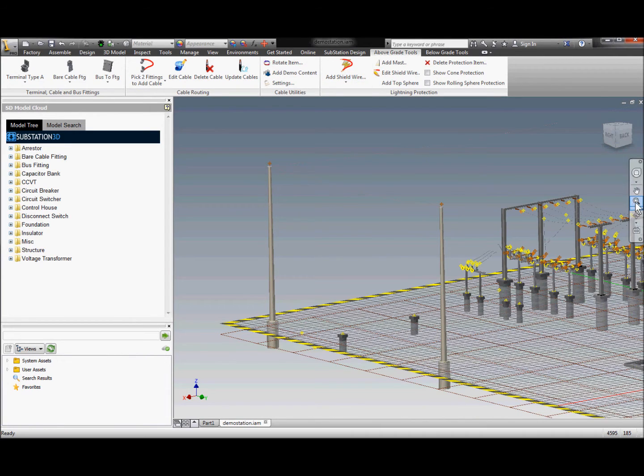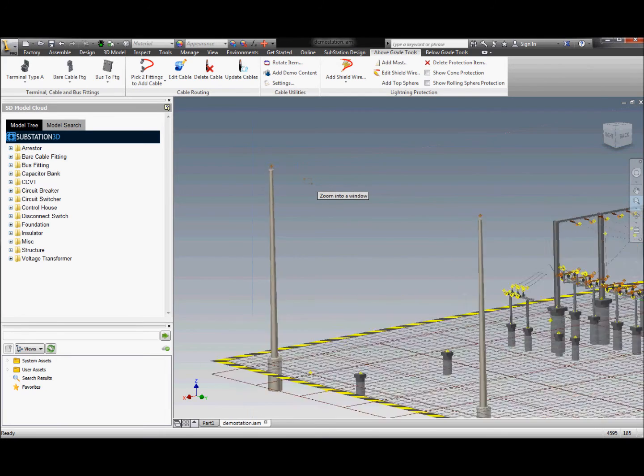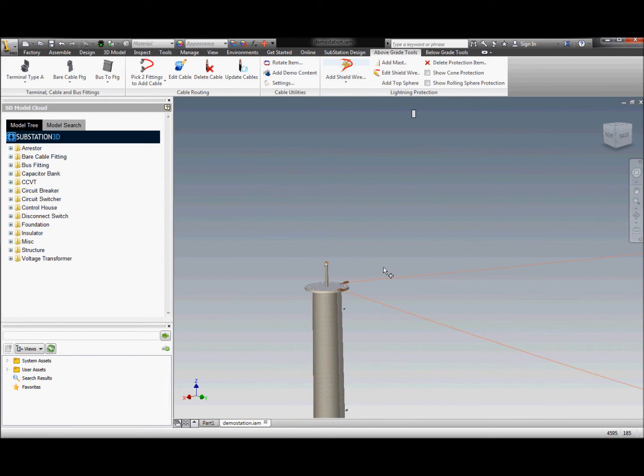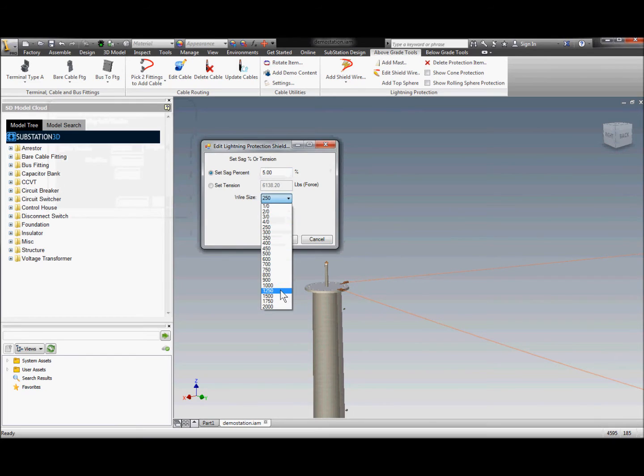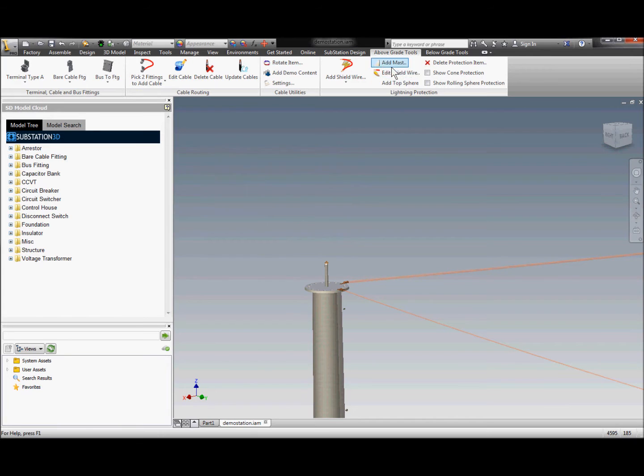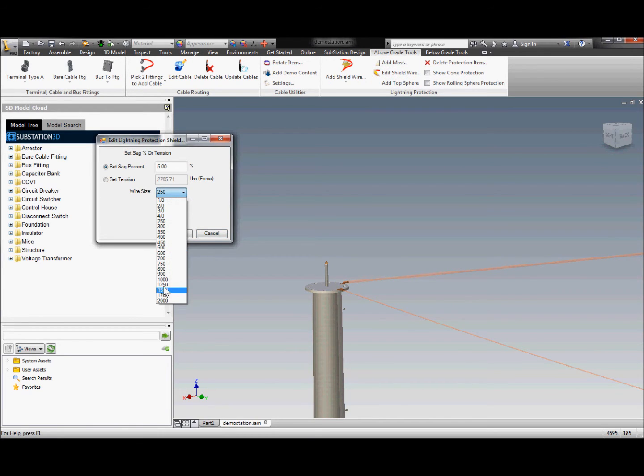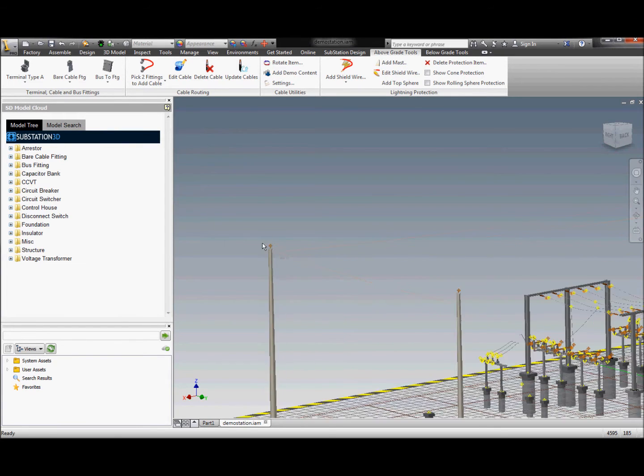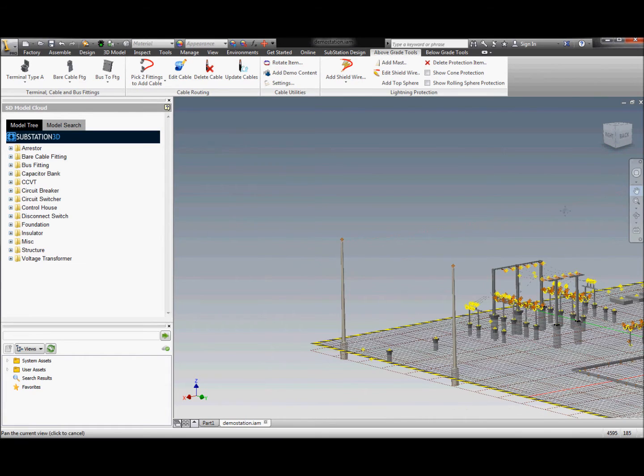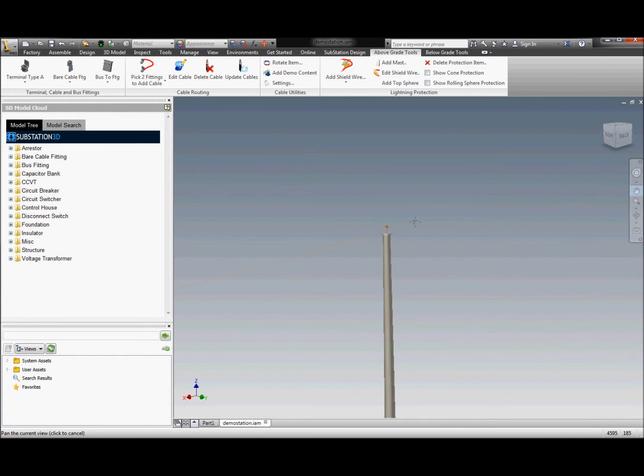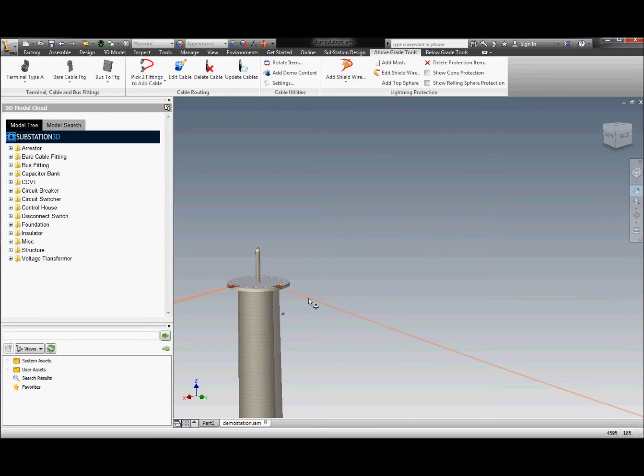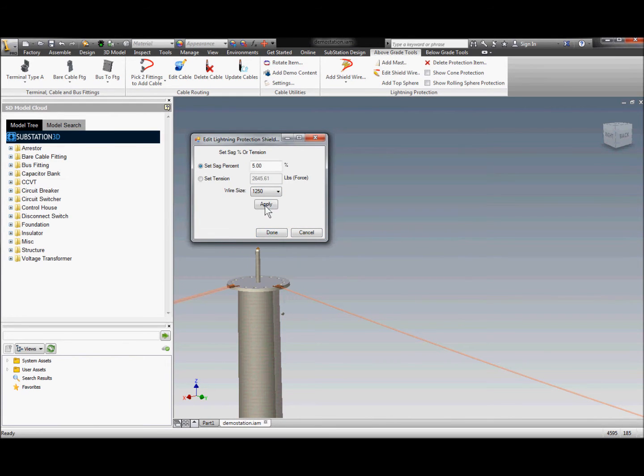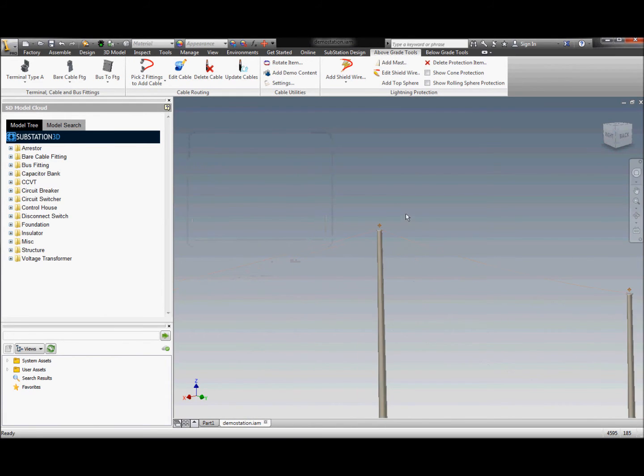The tools take a true representation of both the slope as well as the way the mast angles are touching the ground. We can edit any one of the shield wires, pick a different wire size, and if we have a calculation for the SAG, we can use either the SAG or the tension to calculate that SAG percentage. Editing the shield wire and changing the size of the wire, the SAG is automatically recalculated for the value of that wire size.